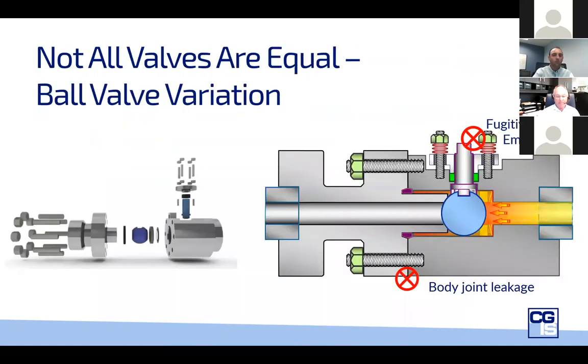In the ball valve world, this is an innovative style called a fixed seat ball. The fixed seat ball was made possible by the development of carbides back in the 1970s and 80s. It wasn't available before because the pressure needed to force that ball onto the integral seat would have damaged metals that were not hard enough. With carbide, they're hard enough to withstand that high force. With this metal-seated valve, we can achieve zero leakage on gases like hydrogen or helium — very small molecules. Its principal use is on steam or on concentrate pipelines.